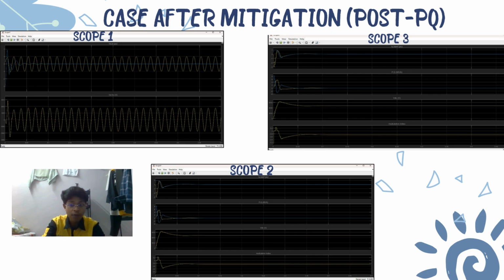In scope 3, it confirms the system-level improvement: the bus B3 voltage is now stabilized between 0.993 and 1.007 per unit, compared to plus minus 4% without mitigation. The reactive power and active power still fluctuate but more smoothly. The distribution STATCOM current clearly follows the 5 Hz flicker pattern, showing dynamic and reliable voltage regulation. This also proves that the STATCOM effectively reduced the flicker to below plus minus 1% and performed real-time reactive power compensation. I think that's all from me.